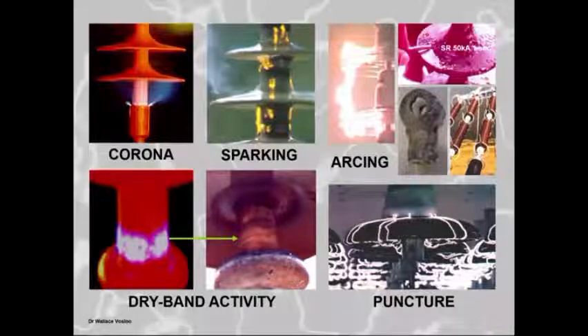After a power arc on a silicone rubber insulator, it normally becomes super hydrophobic because the silicone chains break up into small little chains, which then become available and make it super hydrophobic. On porcelains, obviously, you need arc diverters because you don't have arcing arc diverters. The thermal shock on the porcelain will break the porcelain and you get a line drop. Obviously, the puncturing issue and then your dry band activity, you can see here with the camera where we saw the dry band, and then here you can see the physical dry band. This normally generates a lot of ozone, acids, strong UVC levels, and degrades the polymer in here just because of the actual dry band discharge activity that's there.